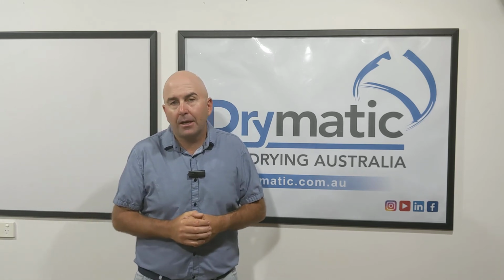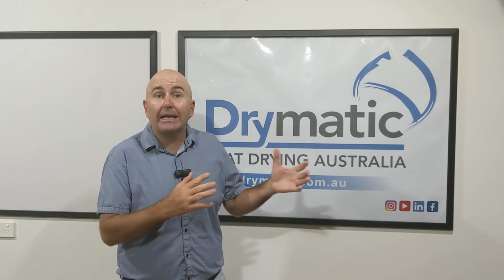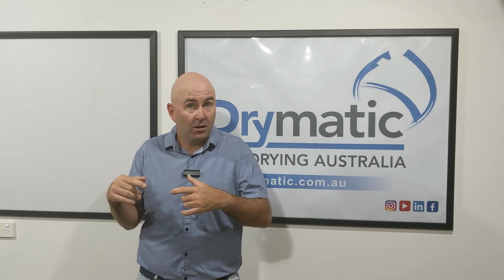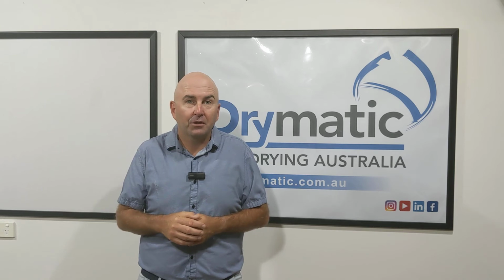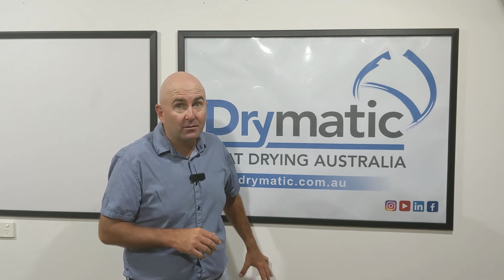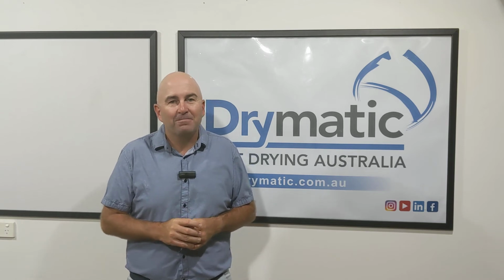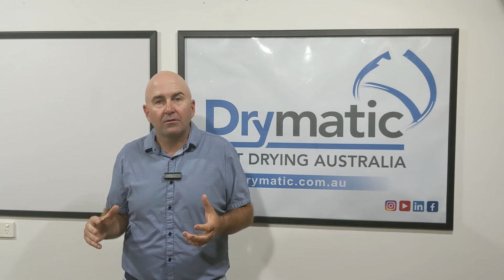A lot of people say to me, yeah, Gary, but now I'm using Drymatic and I'm taking longer to dry. Really? Okay. Is that because you weren't really doing proper moisture detection before, and now, as well as Drymatic, I actually taught you about moisture detection? Oh yeah, you've got a point. Because you weren't checking frames, you were just checking the gyproc. Now you're checking frames. So before you weren't really drying anyway? Oh yeah, you've got a point. Okay, so at the end of the day, Drymatic can be justified, certainly can, but you've got to look at the alternatives, match it up.